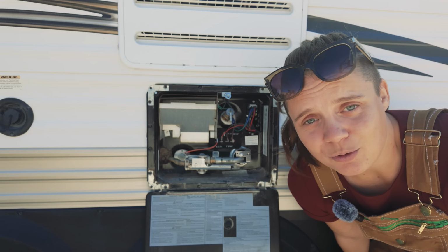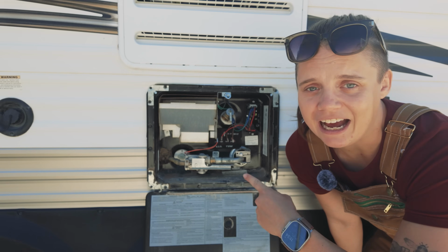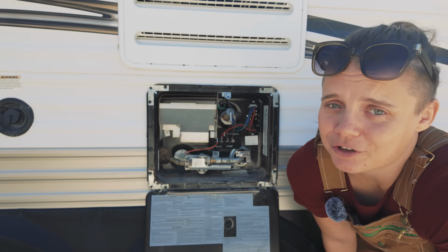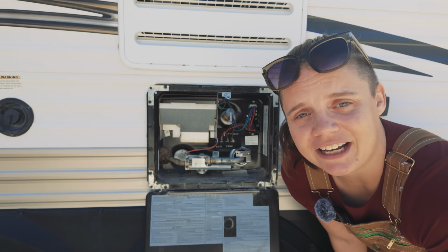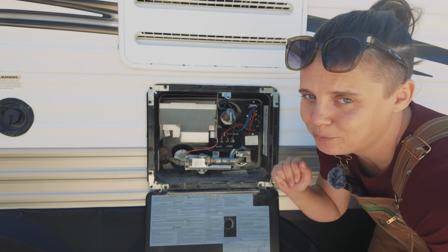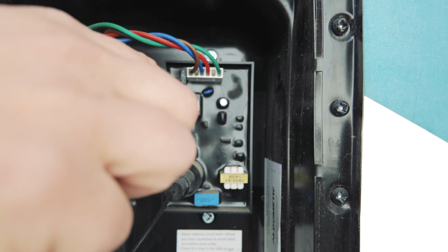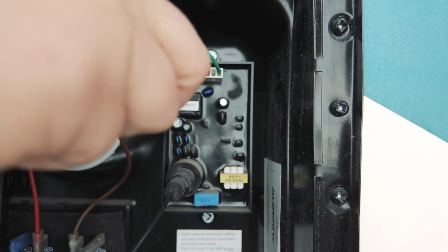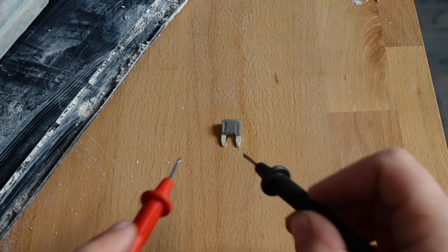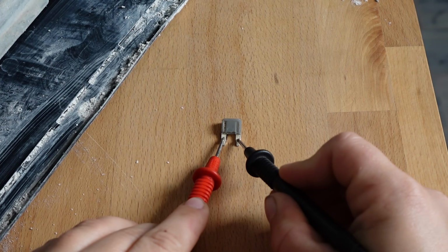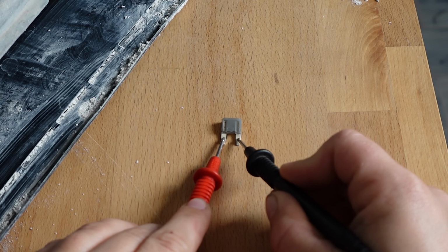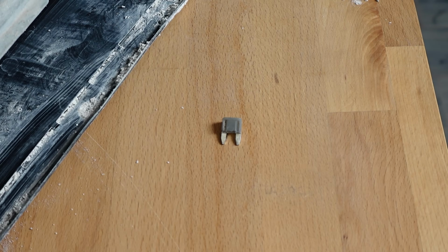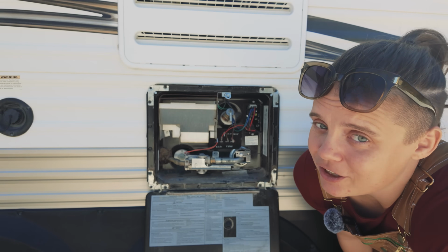If you do not see 12 volts, that points to a bad circuit board. But before you throw it out, check if it has a fuse on it. Take the fuse out and test it for continuity. If your meter beeps, the fuse is good, and that points to a bad circuit board. If it doesn't beep, the fuse is most likely bad—switch it out and see if that solves your problem.